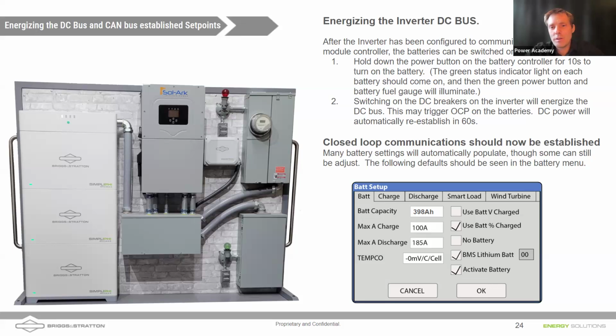Okay, so let's first discuss max charge and discharge. Daniel, on the screen I can see a tab for charge and a tab for discharge. What's the difference between the settings for max charge and discharge on this screen versus the next? Well, these are global settings, so that can be from any power source: solar, grid, generator. Yeah, so if I put 100 amps of charge in here, it's a global setting. If we select 50 amps from the generator, but I also have 60 amps that could potentially be coming from my solar, it's going to limit that overall charge rate to 100 amps. So it won't use any more than 100 amps of DC charging amperage to charge those batteries.